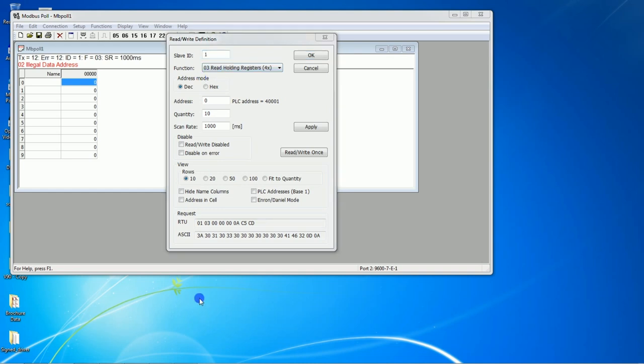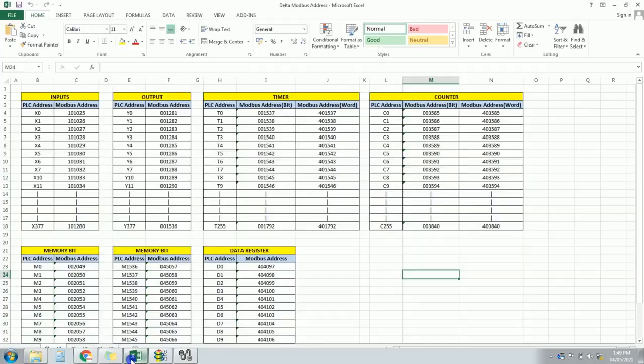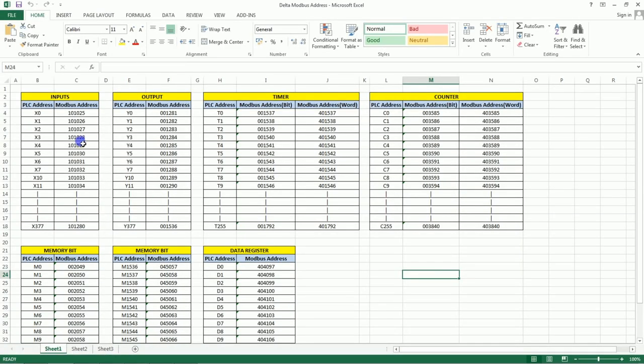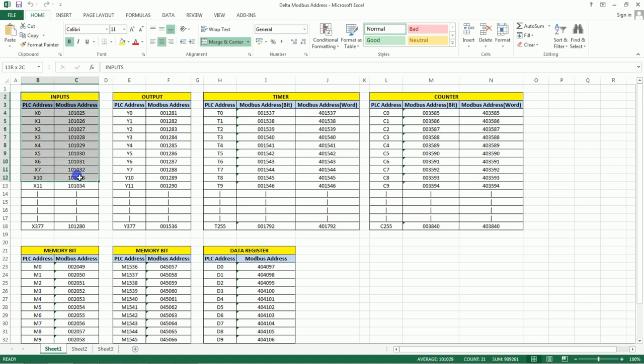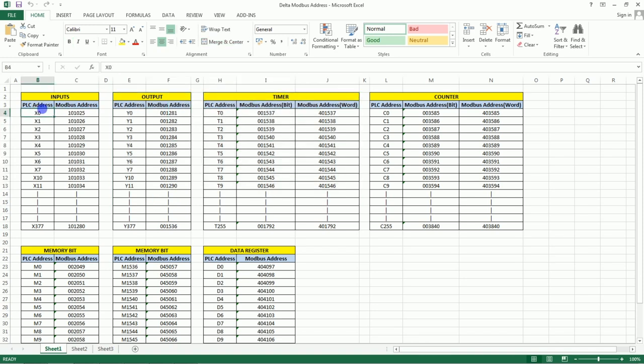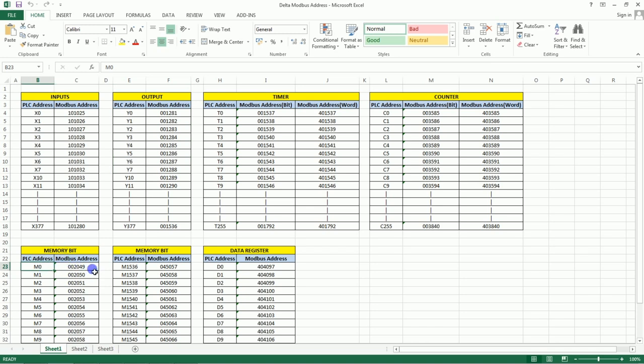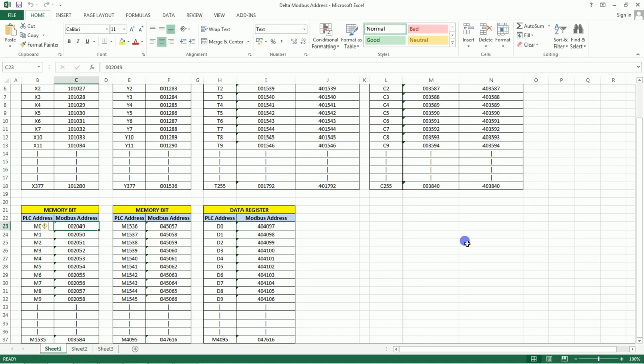First I will show you an address table. This is the address table of Delta PLC addresses and these are the Modbus addresses — I have differentiated all of these. For inputs these addresses are used, for outputs these addresses are used, for inputs you can see X0 is the PLC address and for Modbus address we use the mapped address. M0 for PLC address and 2049 is the Modbus address. I will share this sheet in the description via a Google Drive link — you can download it from there.